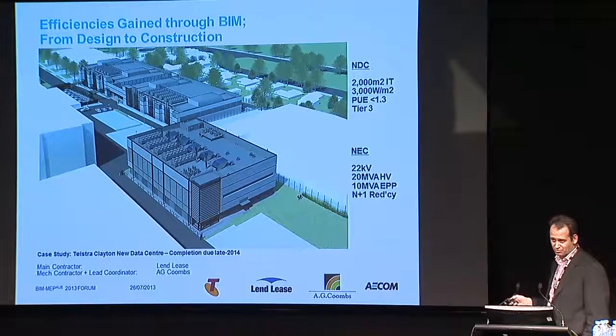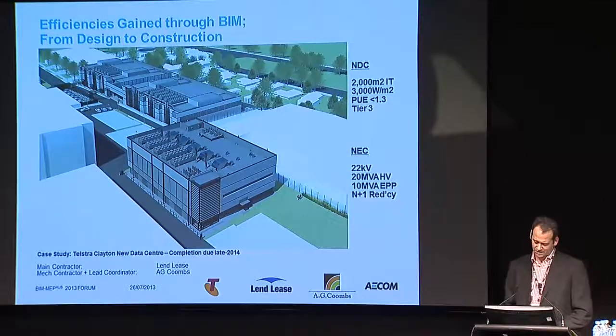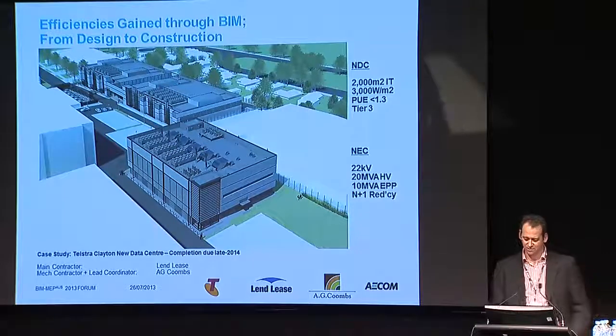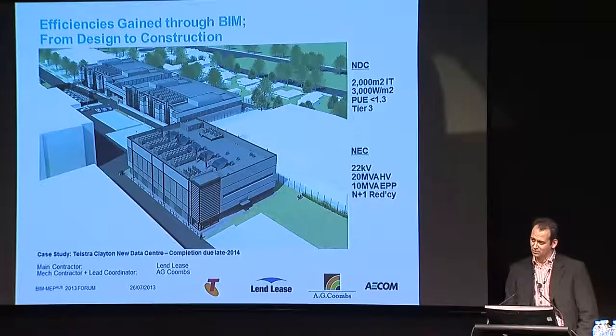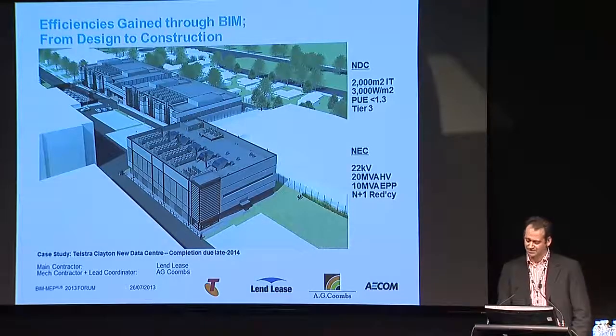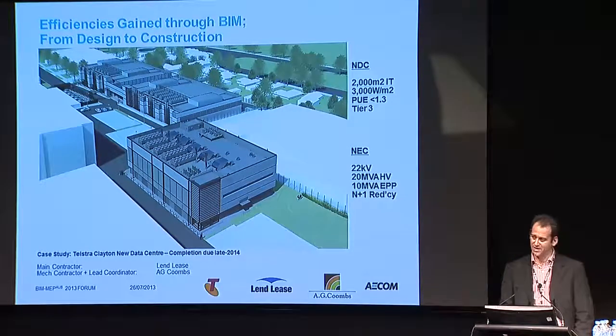The intent was to provide additional power and EPP for the new data centre building. So the NEC, or New Energy Centre, is a high voltage facility, 22 kV with a 20 MVA HV capacity, taking supply in from the utility. It has extremely high levels of complexity with regards SCADA, PLC, and HV protection requirements. It has 10 MVA of EPP, or emergency power generation, and N+1 redundancy throughout all its systems - highly complex, feeding the data centre.